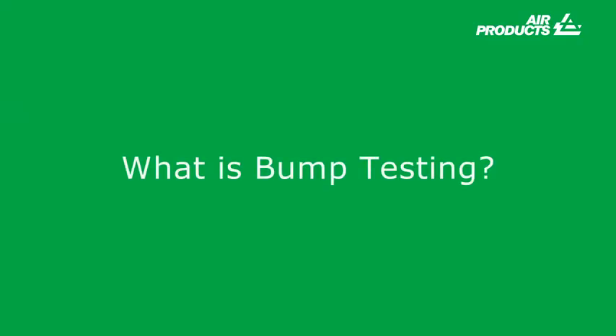So what is bump testing? Bump testing is the application of standard test gas to a detection instrument to verify the functionality of sensors and alarms, not its accuracy. In previous years, the reasons for this may have been difficult to understand. In addition, misleading information about the so-called maintenance-free instruments led to a misplaced sense of security.